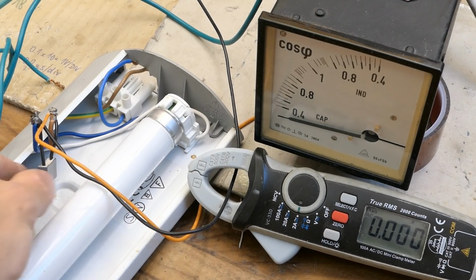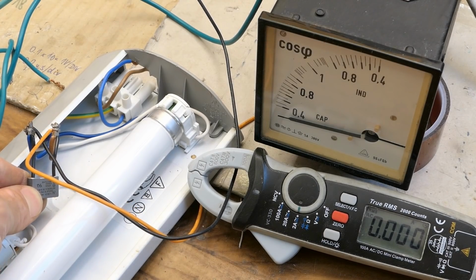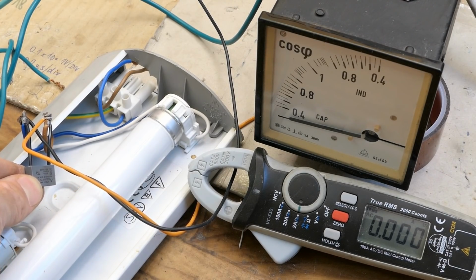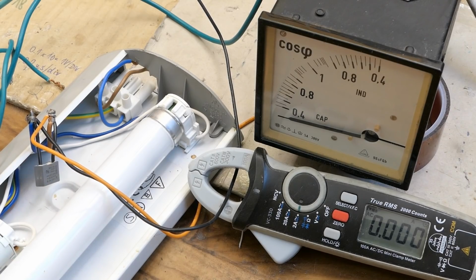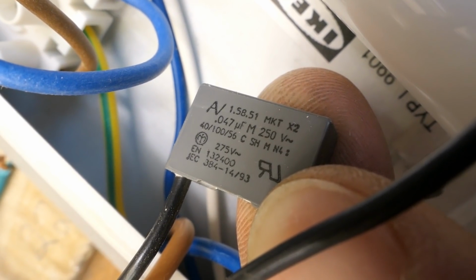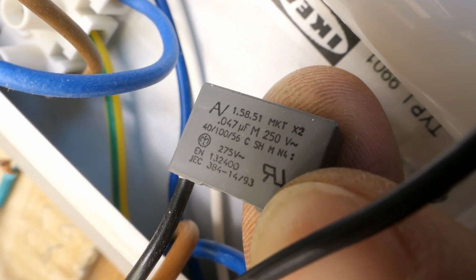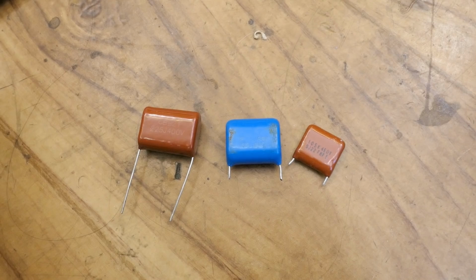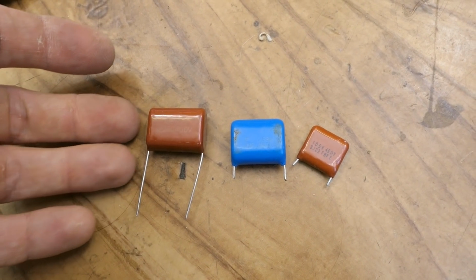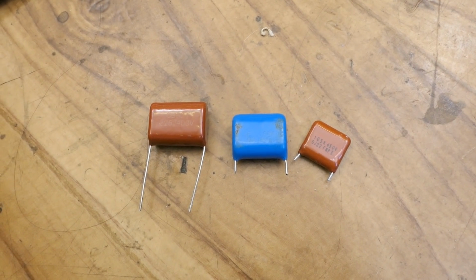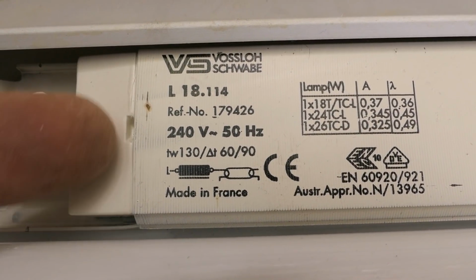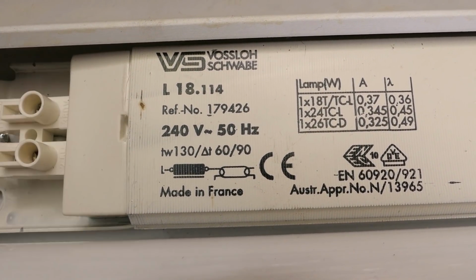And they might have just a tiny capacitor, but this one is just for interference suppression. Such a tiny one is not for the compensation. For a power factor compensation, it needs much more capacitance than this. This tiny interference suppression capacitor is just 0.047 micro, but for the right compensation it needs about 3 or 4 micro, way more. And that's the marking of the inductor in the fluorescent fixture.